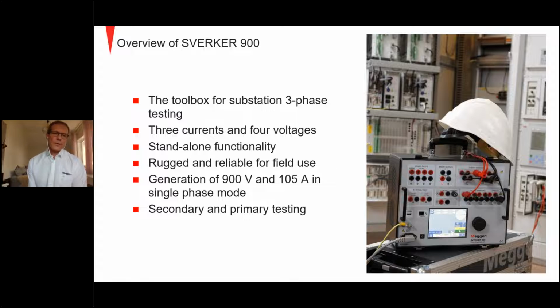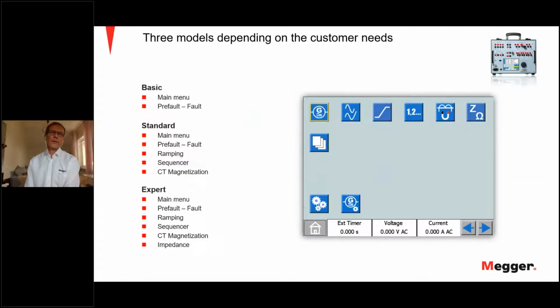And also, if you're in individual mode, you can use it for doing secondary injection in the relay, to test phase-wise as a relay test instrument. So it's used for doing secondary and primary testing in the substation, covering a lot of tests. Also, the Sverker 900 actually has three models: the basic one, the standard model, and the expert model.